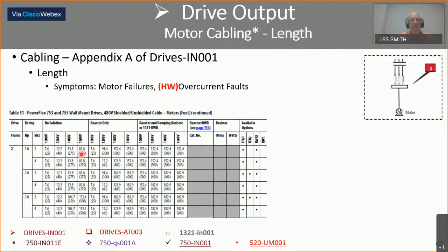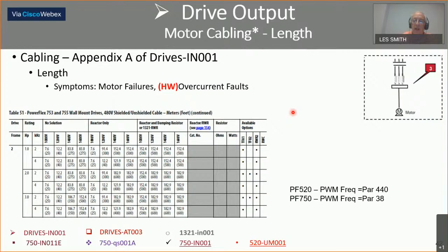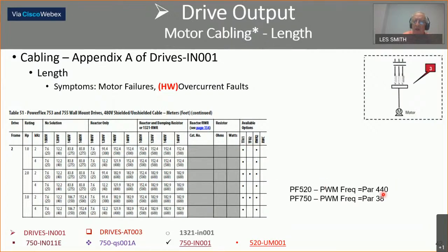The lighter the load, the faster the switching time also. So the worst case would be a small drive that is lightly loaded, which has the fastest switching time. Regarding PWM frequency: parameter 440 in the 520 and parameter 38 in the 750 — set them to their lowest value. This will cut your chance of problems in half as far as switching time goes. Normally you'll go from four kilohertz down to two.